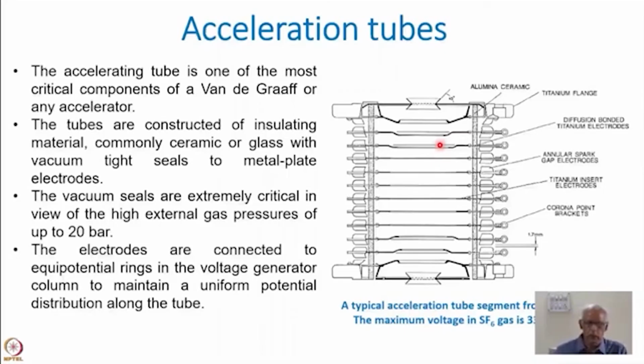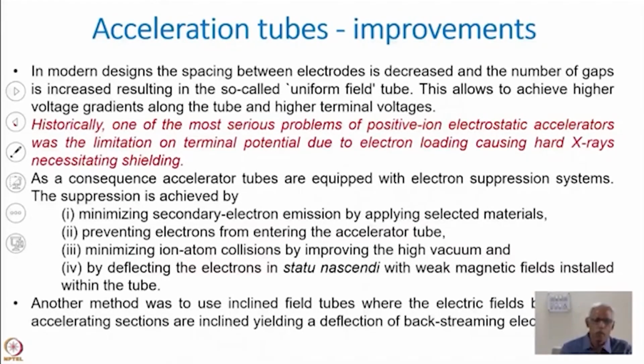The electrodes are connected to equipotential rings in the voltage generator columns to maintain the uniform potential distribution. Because for focusing the beam, it is very important to have accurate beam this voltage distribution.